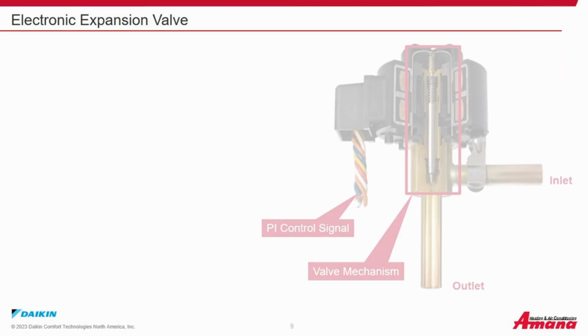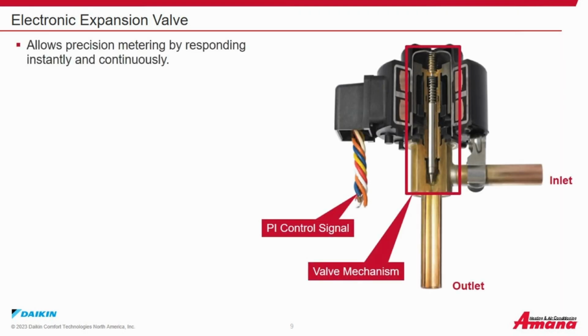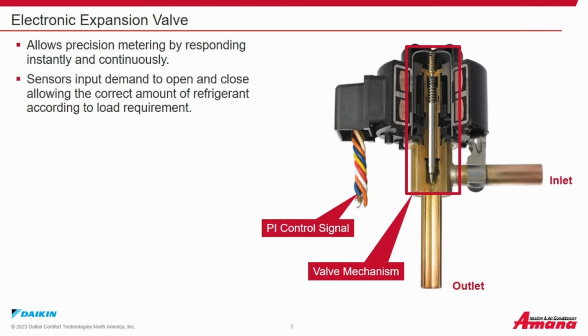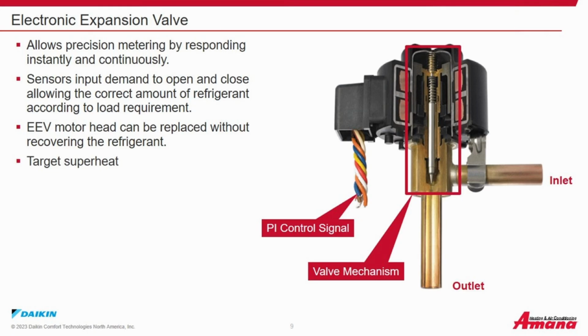The electronic expansion valve allows precision metering by responding instantly and continuously. Sensors input demand to open and close, allowing the correct amount of refrigerant according to the load requirements. The EEV motor can be replaced without recovering the refrigerant. The target superheat in cooling is 9 degrees Fahrenheit, metered at the indoor EEV, and in heating 7 degrees Fahrenheit, metered at the outdoor EEV.